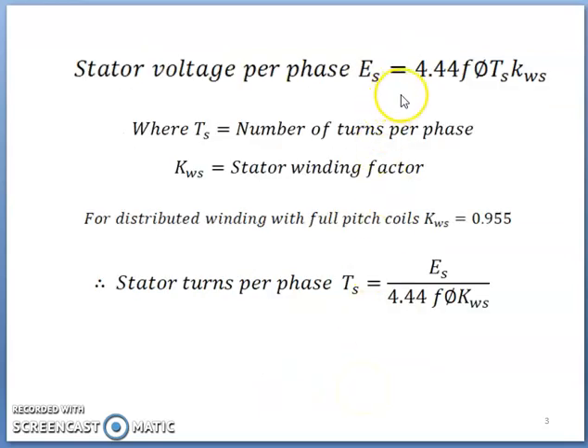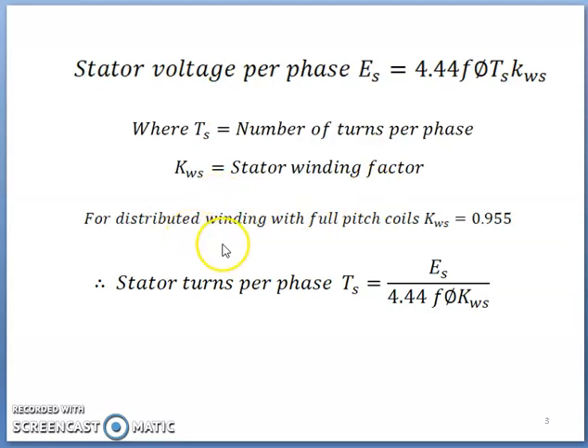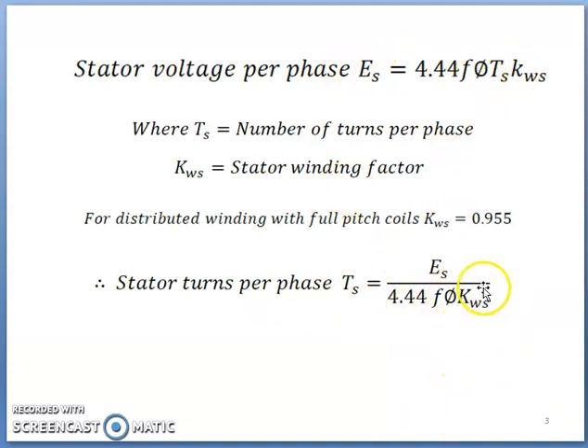Stator voltage per phase Es is given by Es = 4.44 * f * phi * Ts * Kws, where Ts is number of stator turns per phase and Kws is the stator winding factor. The stator winding factor is the product of pitch factor and distribution factor. For full pitch winding, pitch factor is 1, and for 60-degree spread winding, the distribution factor is 0.955. Therefore for distribution winding with full pitch coils, Kws equals 0.955. From this equation, stator turns per phase Ts equals Es divided by 4.44 * f * phi * Kws.